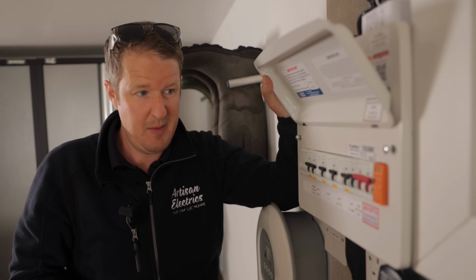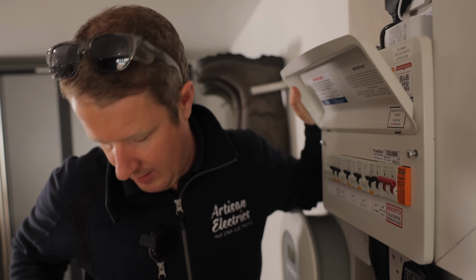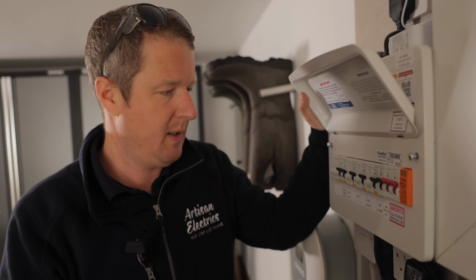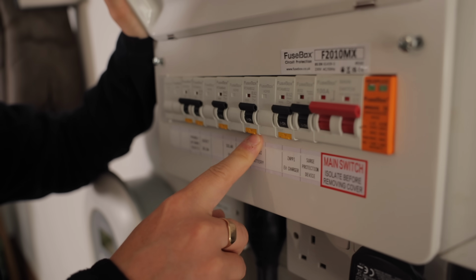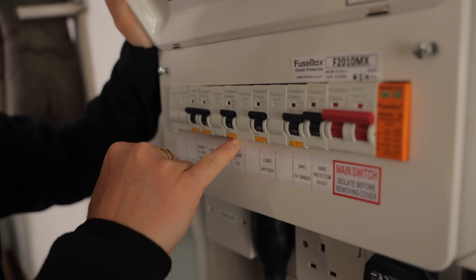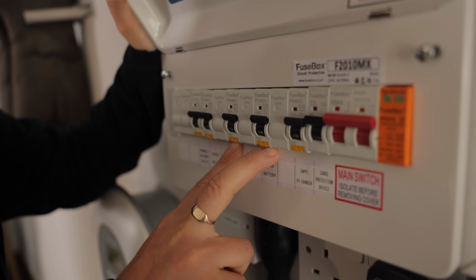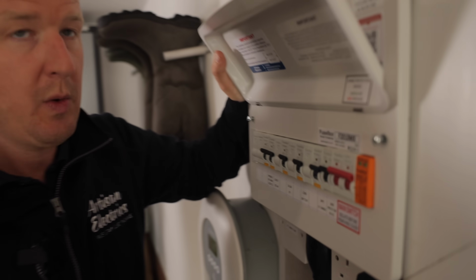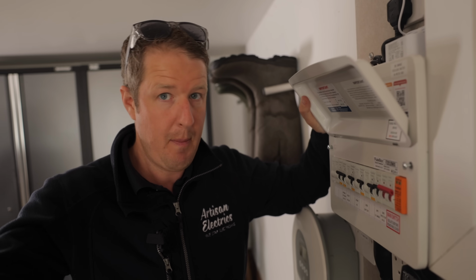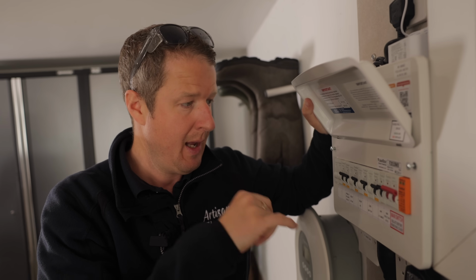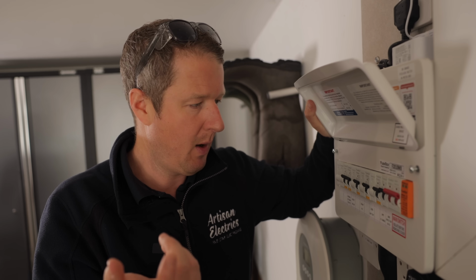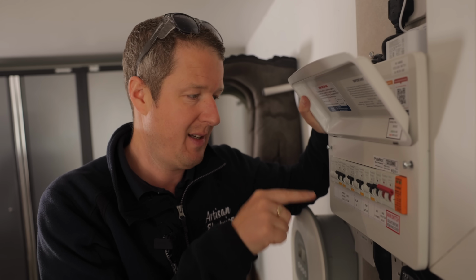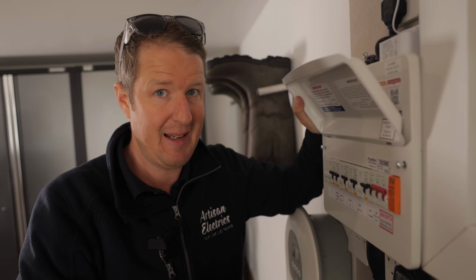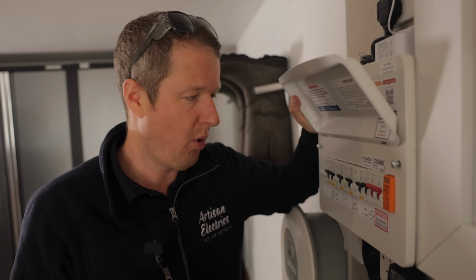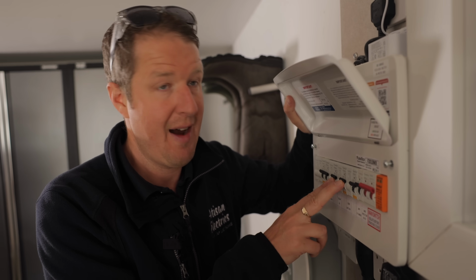Now I've got a confession to make. We made a little mistake when we did the install here originally: we put the Libbi circuit on an RCBO, and we also put the SolarEdge inverter on an RCBO. We later found out that Fusebox RCBOs are not bidirectional, meaning they can't feed power back through them into the system. It works, but apparently if you press the test button while it's feeding power back into the system, it won't work properly. So we're going to swap these out for MCBs.